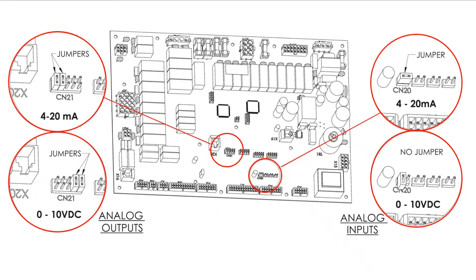Next we'll talk about external controls. Before we talk about the navigation, there are pins and jumpers that have to be in the correct position on the circuit board. This slide came from our manual. For example, on pin number CN21, if you're choosing a 4-20 milliamp analog output, you want your jumpers on pins one and two. If you want zero to ten output, your jumpers go on pins four and five. On the inputs, pin number CN20 — if you chose 4-20 that's the jumper position, or if you chose zero to ten volt DC, there's no jumper position in vertical position.